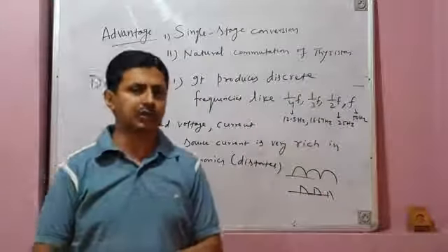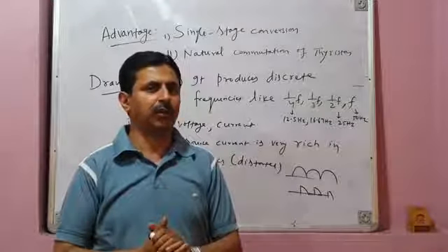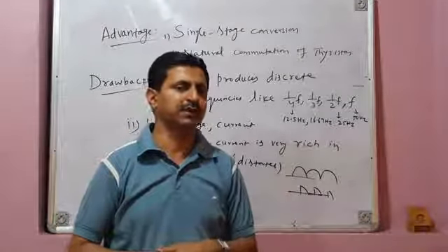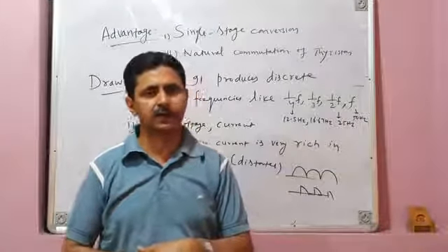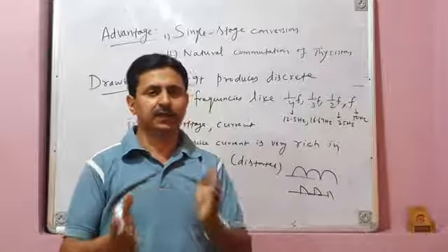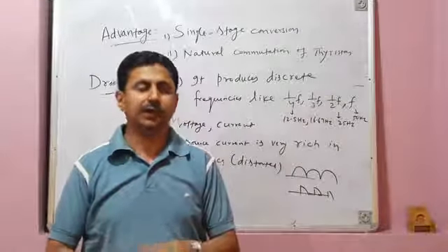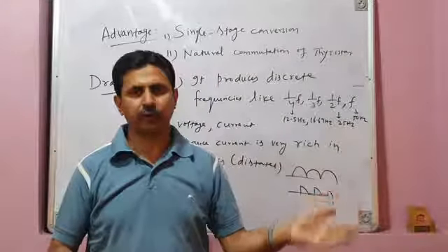So load voltage is distorted. And if your load is an induction motor, you know, the induction motor has to carry large, strong harmonic components of current in the windings, which will increase the eddy current losses, which will increase the hysteresis loss, which will increase the harmonic losses in the machine. It will result in vibrations, harmonic torques, pulsations, and other problems.